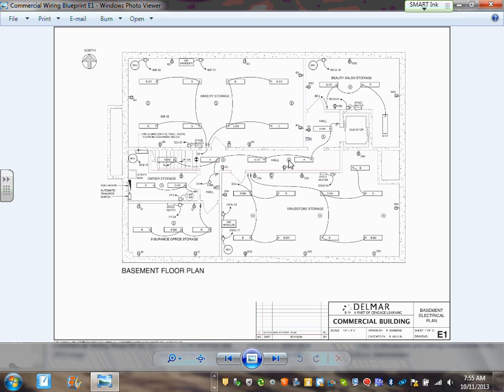Brian, my friend, this is another example for you, and now you have a few other examples, of how to do a commercial building. The reason why I like this book is that it's a multi-occupant building. The one that I asked you guys to design is only single occupant. What's the difference? One meter feeds the whole building, versus multiple meters feeding separate parts of the building. That's the only difference. Right?